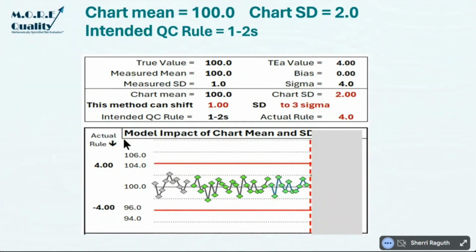And most methods have a sigma above 6. Why we started saying 3 sigma is acceptable in labs, I do not know. I've recently seen publications that say 2.35 sigma is acceptable because you're only going to fail CLIA if 1 sample in 5 fails. So I'm willing to report 20% error and I'll still pass CLIA.